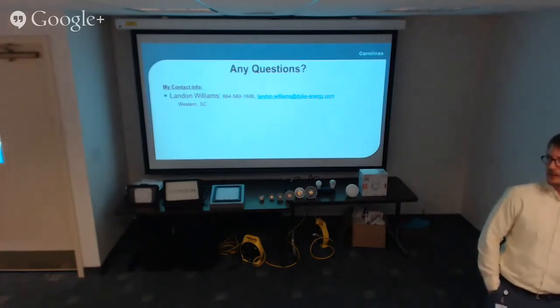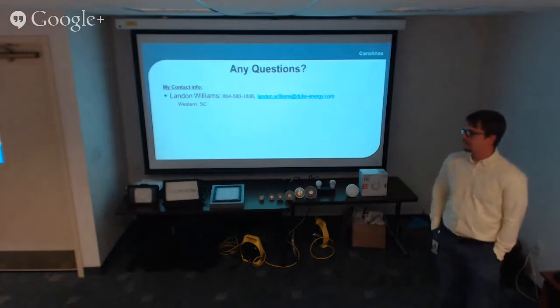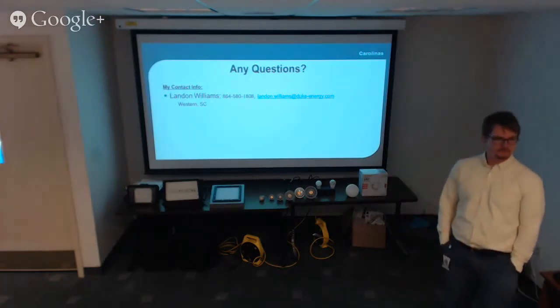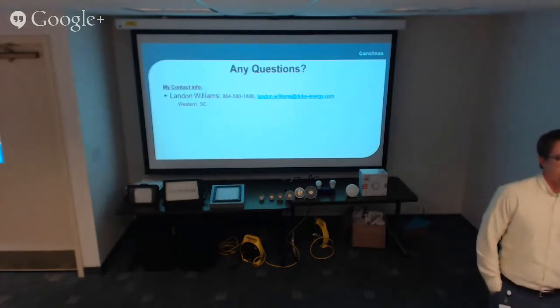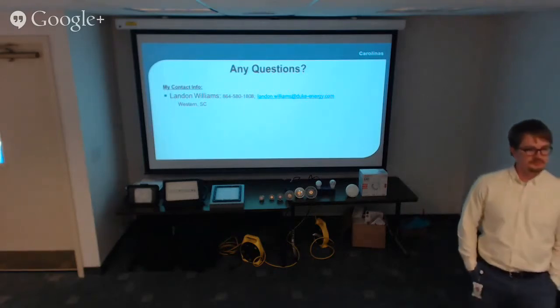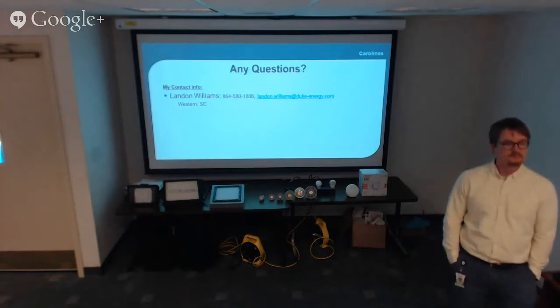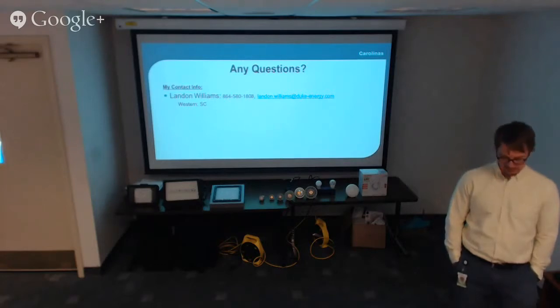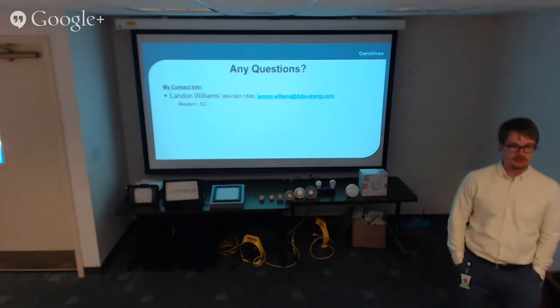Anybody else? Scott mentioned something about saving money. Anthony Smith, are you here? Do you want to speak about what you've done recently at your facility? Well, twice we've taken advantage of this program. The first time we retrofitted 500 T12 fixtures, and it was about a $24,000 project. After we sent the completion form and a copy of the invoice to them, within a week I had a check for $8,600. Another time we replaced a 20 horsepower VFD on an air handler, and that was $2,000 right there. I was real happy with the response. One week, and we had a rebate. Sure, that's great. Thanks for that.